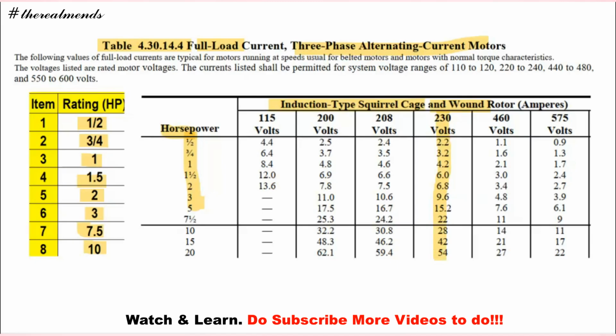Okay, so yung ating 1/2 HP, so meron FLC na 2.2 amperes. Pag 3/4, meron 3.2 amperes. Pag 1 HP, merong 4.2 amperes. Pag 1.5, that is 6 amperes. Pag 2 HP, we have 6.8.